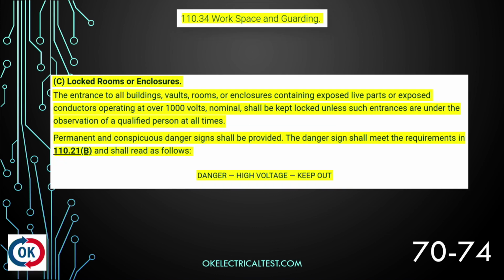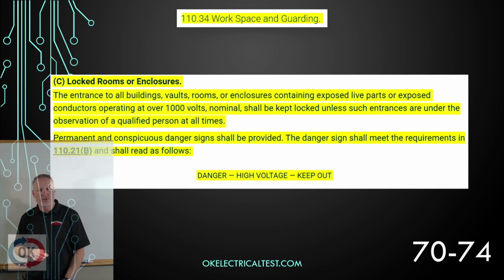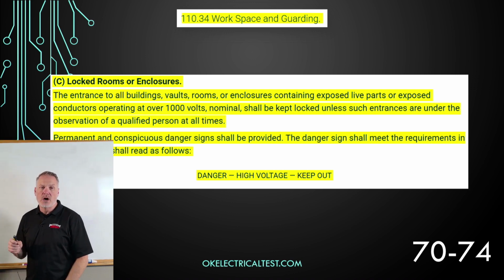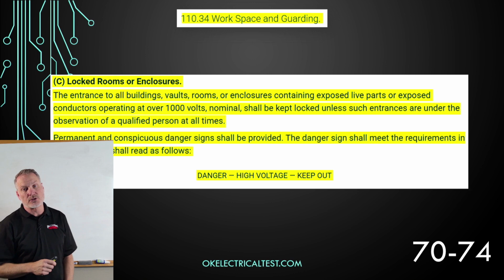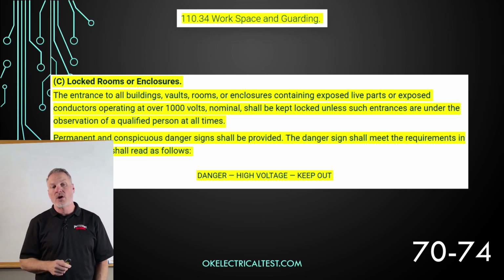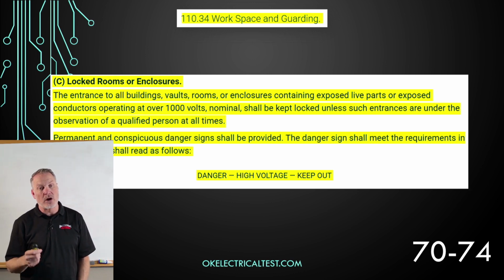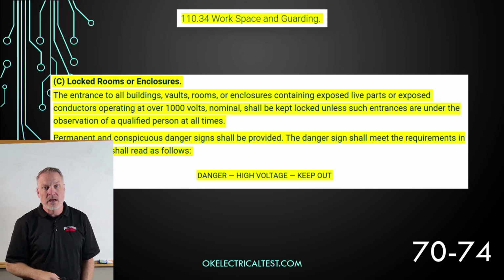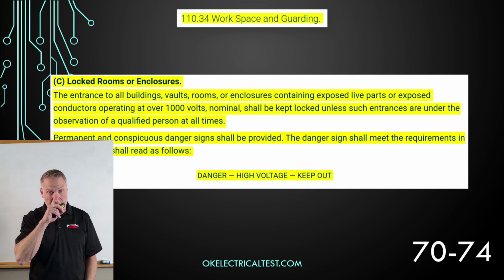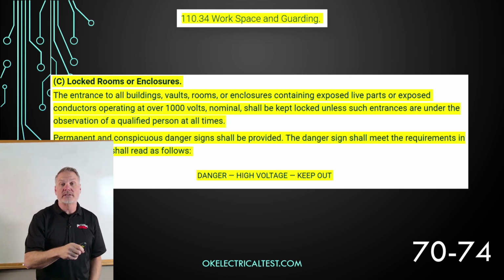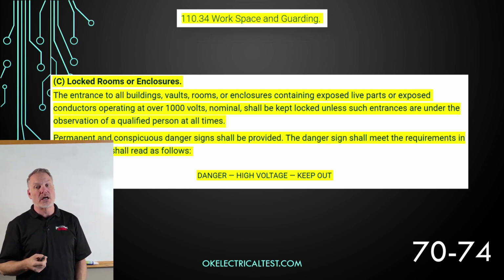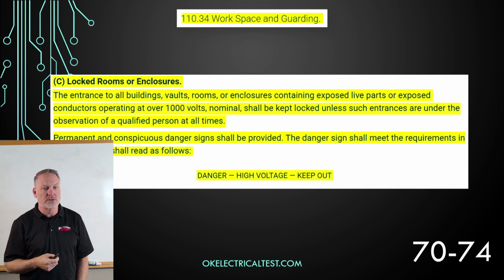110.34, workspace and guarding. We're going to go down to letter C, locked rooms or enclosures. The entrance to all buildings, vaults, rooms, or enclosures containing exposed live parts or exposed conductors operating at over 1,000 volts nominal shall be kept locked unless such entrances are under the observation of qualified persons at all times. So we can have it locked, or we can have some sort of guard on duty guarding those electrical enclosures.